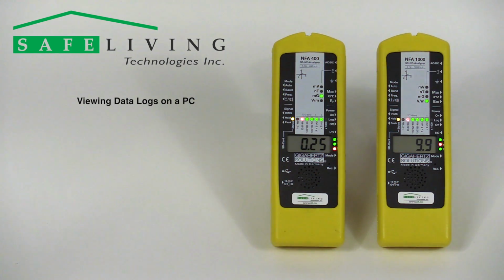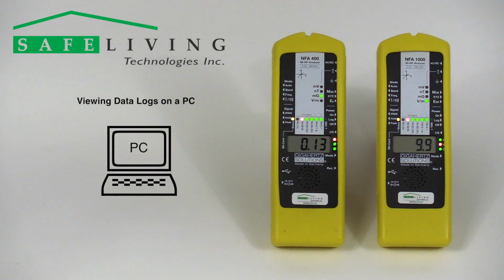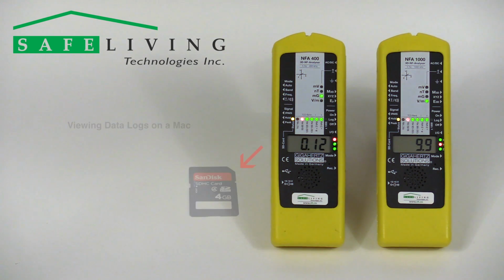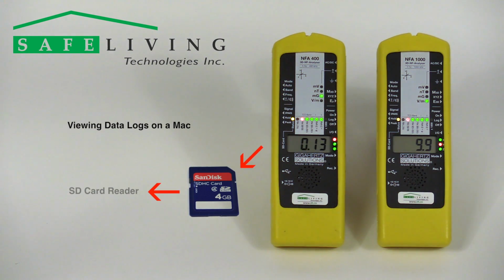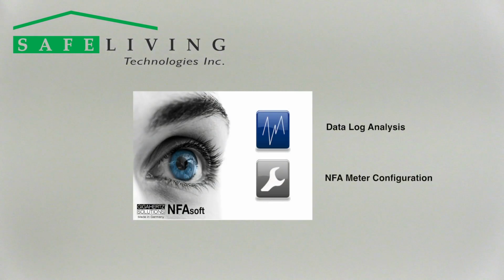If you choose to log data on the NFA1000 or NFA400, you will need to view it on a PC or Mac. Using a PC, the meter can be connected directly to an available USB port to view data on the included 4GB SD card. However, the meter's USB port is not compatible with a Mac. When using a Mac, the SD card must be removed from the meter and inserted into an SD memory card reader. The software used to look at this data is called NFASoft.